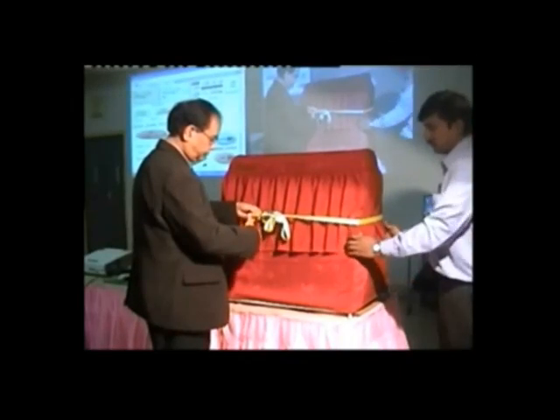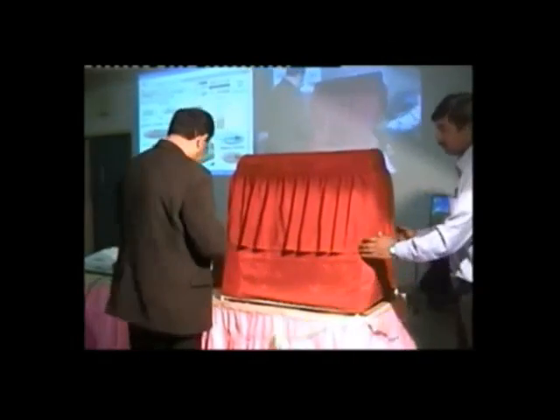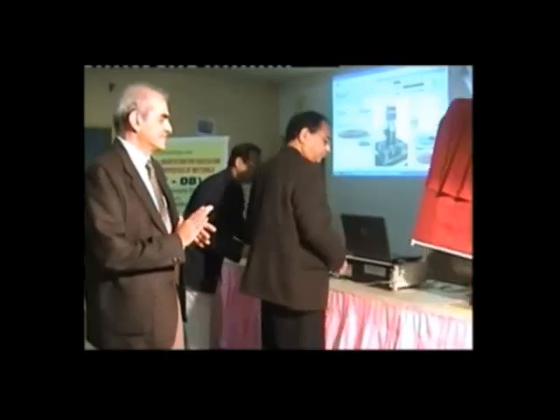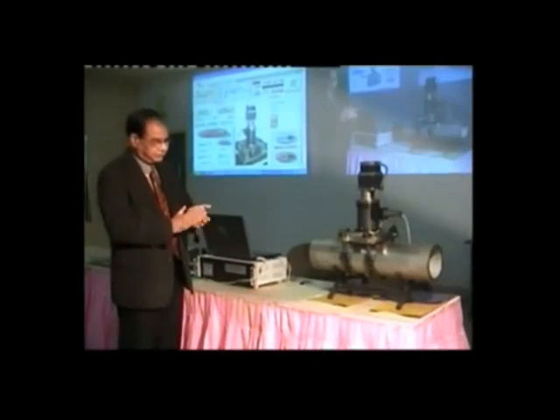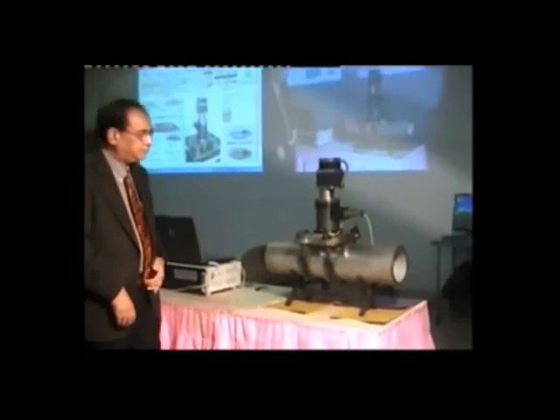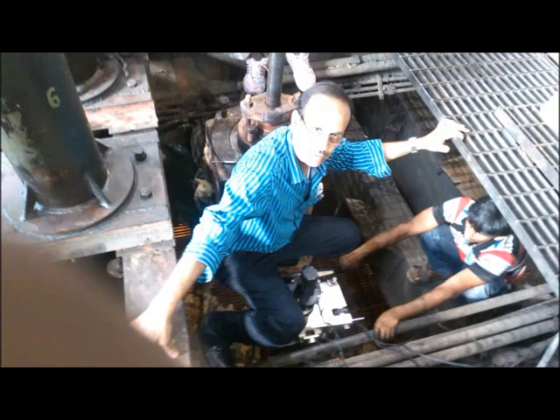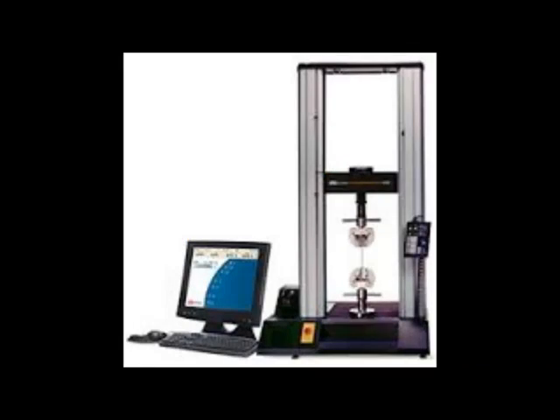Developed a portable automated ball indentation technique known as PABI system for in-situ evaluation of mechanical properties. For assessment of integrity of critical components that experience materials degradation during service, it is necessary to obtain the mechanical properties of the materials.